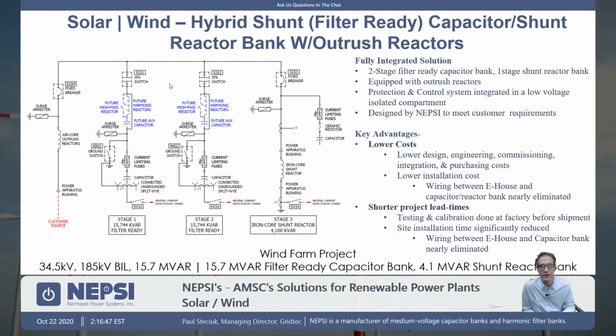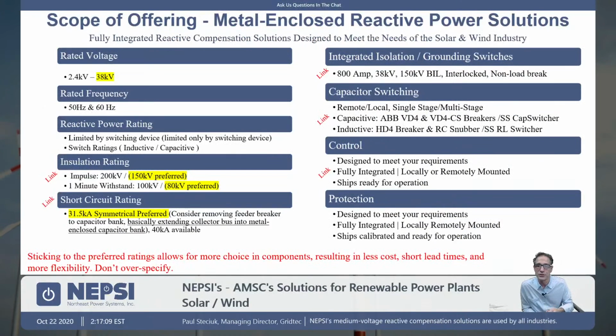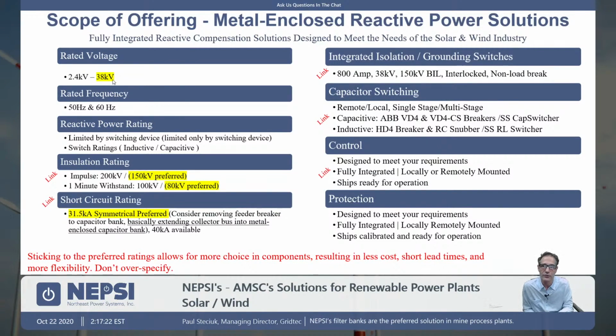The capacitor stages here, we're going to be talking about these switching devices here. And again, capacitor switching at the medium voltage level, 38 kV, is also something that can be difficult for the switching devices. So we're going to be talking about what choices we have in the switching devices here, because that overall determines the cost of the equipment and also the footprint of the equipment and the lead time of the equipment. So we're going to talk about the metal-enclosed solution, how it gives you choice. When you're in an open air solution, you really do not have a lot of choice of your switching solution. So let's just summarize here. Since we're in the renewables area, we're sitting at that 38 kV level. So 34.5 kV is the nominal, multiplied by 1.1, and you get about 38 kV.